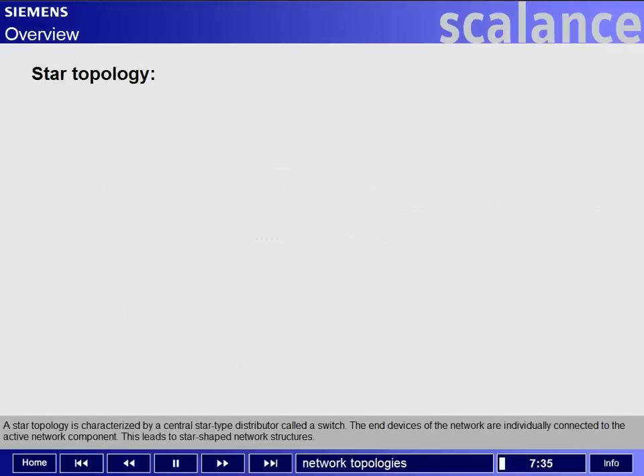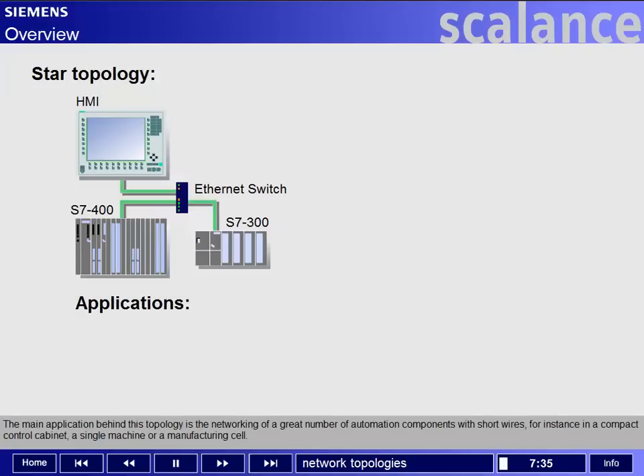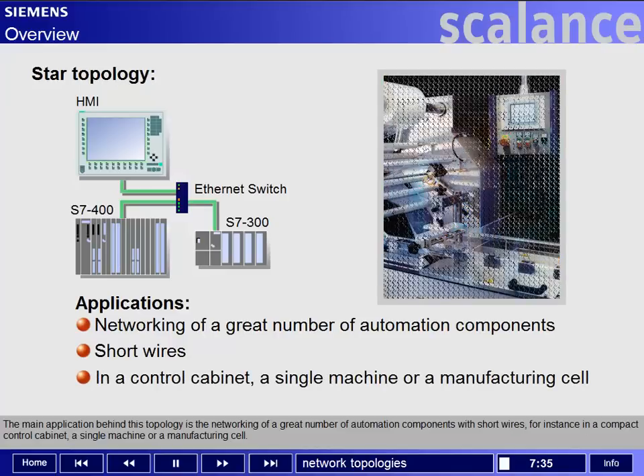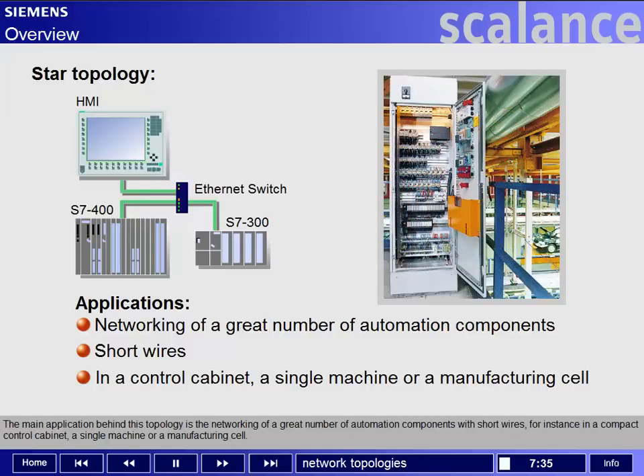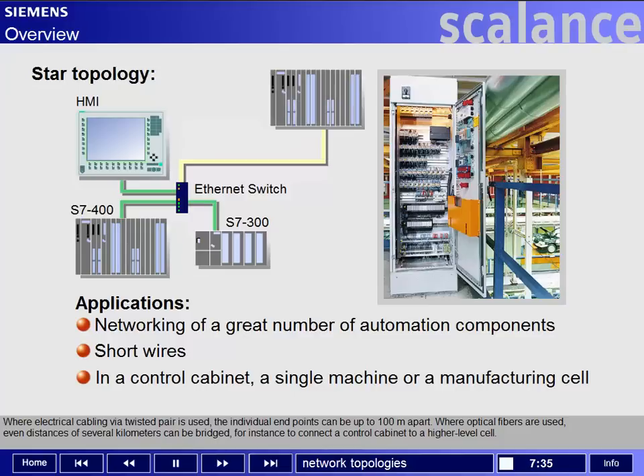A star topology is characterized by a central star-type distributor called a switch. The end devices of the network are individually connected to the active network component, leading to star-shaped network structures. The main application behind this topology is the networking of a great number of automation components with short wires — for instance, in a compact control cabinet, a single machine, or a manufacturing cell. Where electrical cabling via twisted pair is used, the individual end points can be up to 100 meters apart. Where optical fibers are used, even distances of several kilometers can be bridged — for instance, to connect a control cabinet to a higher-level cell.